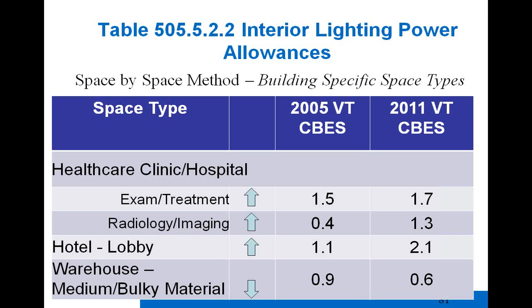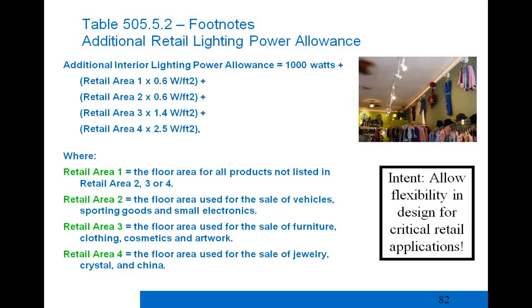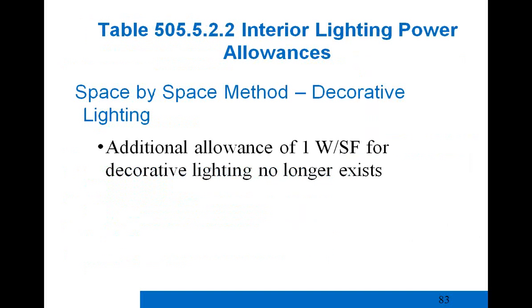For retail applications, the code tries to provide a lot of flexibility since retail is a lighting-critical application where energy efficiency, aesthetic, and sales criteria must all be balanced simultaneously — that flexibility is outlined in the code with exceptions and additional calculations. When calculating proposed lighting power, you must sum the wattage of all connected lighting: overhead, task, and decorative. Wattage must be calculated based on actual power draw capacity, not nominal lamp rating — if a fixture can take 100 watts, you count 100 watts even if only a 25-watt bulb is installed.